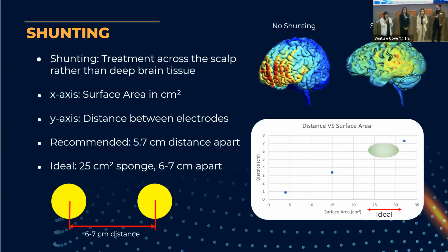So since we would use a 25 centimeters squared sponge and electrode treatment, we would need these to be 5 centimeters distance apart, measured from one center of the electrode to the other center of the electrode. However, in our testing, we were able to push this to 6 to 7 centimeters apart.